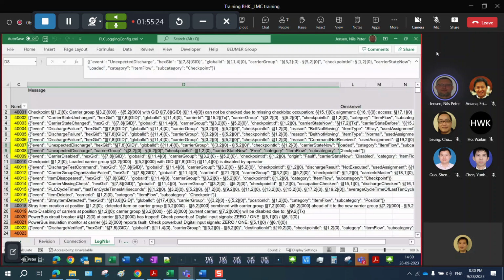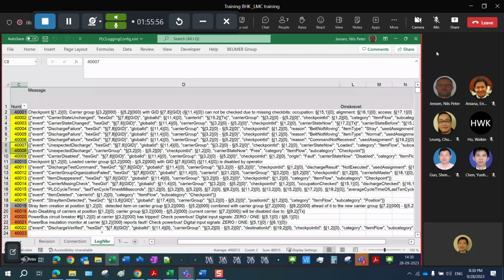And this is an indication that the offset to the CTDs needs to be adjusted, because we are giving a discharge command for a carrier, but the command actually hits another carrier than what we expect. So it's very important that those two are not present in the logs.